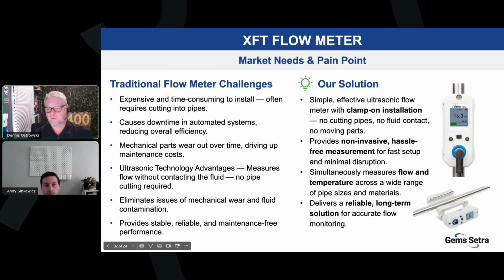Okay. The reason that we are launching this new product is because of the challenges that you will often see with traditional flow meters. Traditional flow meters are the ones that are actually in line in the pipe. You have to cut into a pipe. Any instrument that's in line in a pipe causes a pressure drop. You have mechanical parts that could wear. Sometimes the media has to be pure or potable, in which case you have to have parts in your device that are compliant with that. That could be expensive and hard to come by.